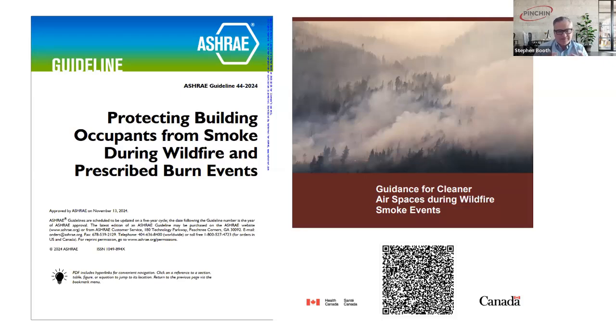The Health Canada guidance is similar, aiming to create and operate public and private buildings as safe havens during smoke events. Key points include maintaining lower PM 2.5 concentrations than outdoors, keeping CO concentrations below 10, keeping CO2 concentrations below 1,000, and maintaining relative humidity within a comfort range.